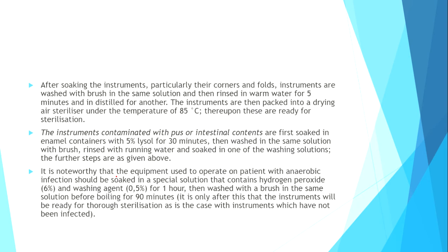It is noteworthy that the equipment used to operate on patients with anaerobic infection should be soaked in a special solution that contains hydrogen peroxide 6% and washing agent 0.5% for 1 hour. Then it is washed with a brush in the same solution before boiling for 90 minutes. It is only after this that the instruments will be ready for thorough sterilization, as in the case with instruments which have not been infected.